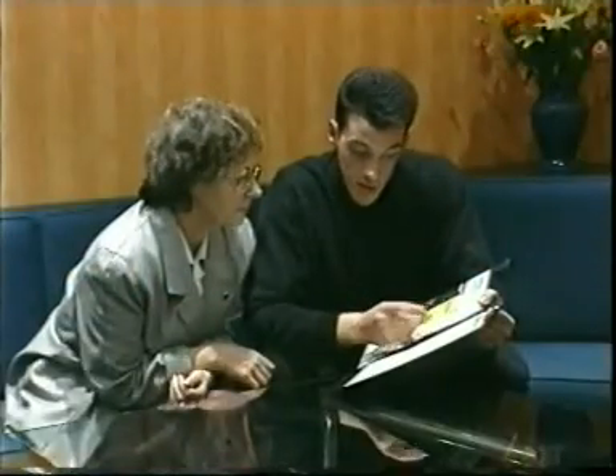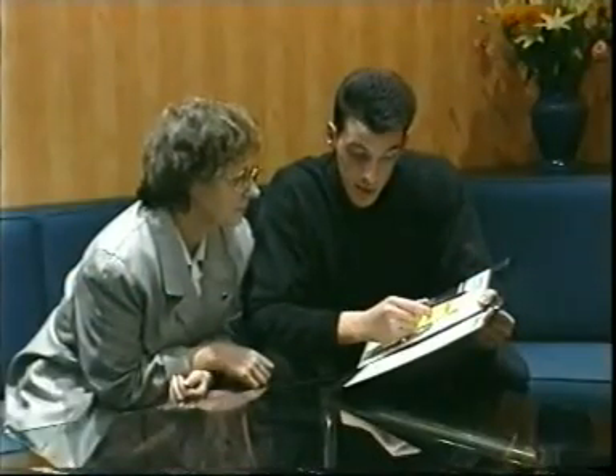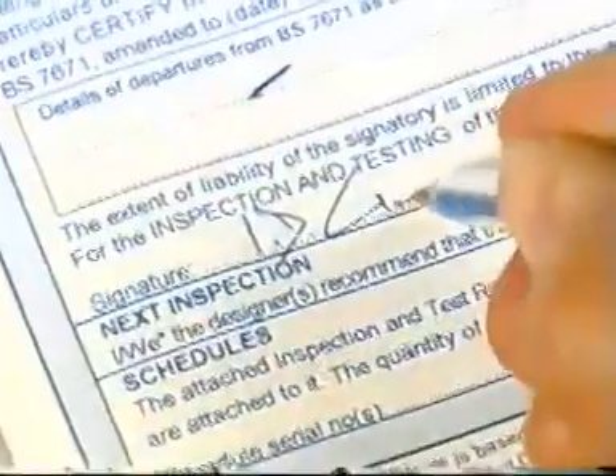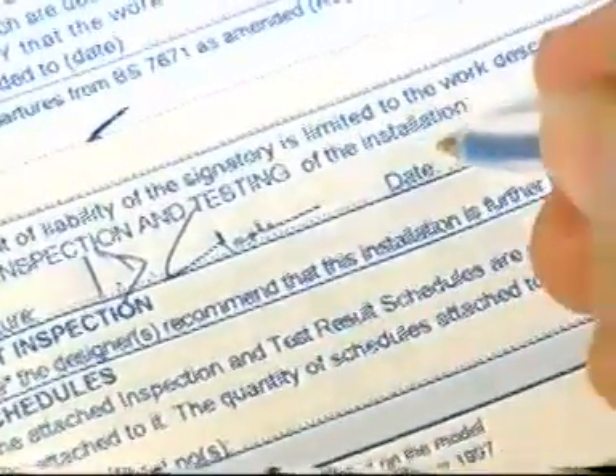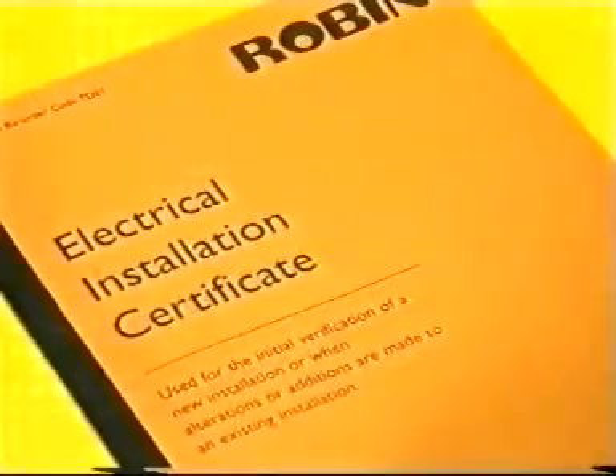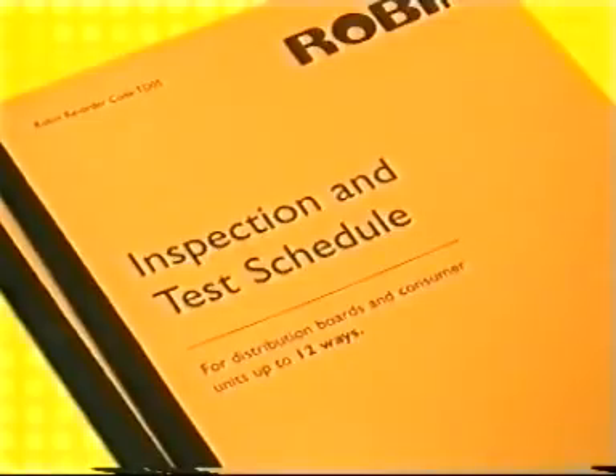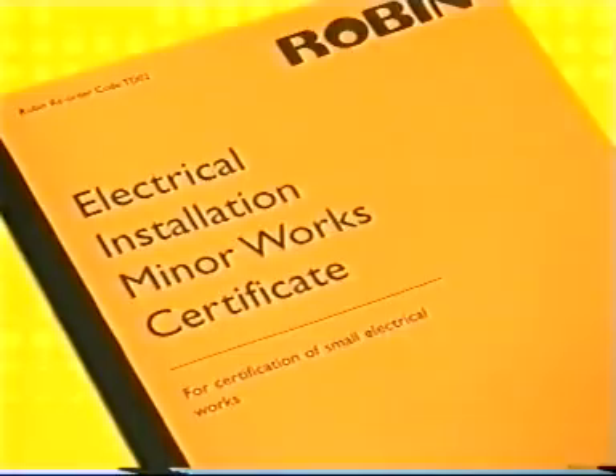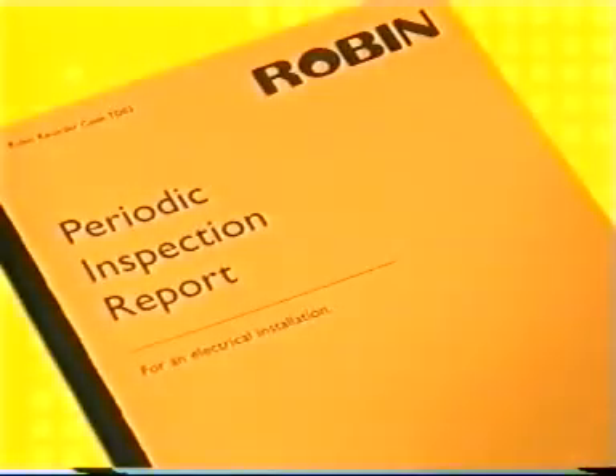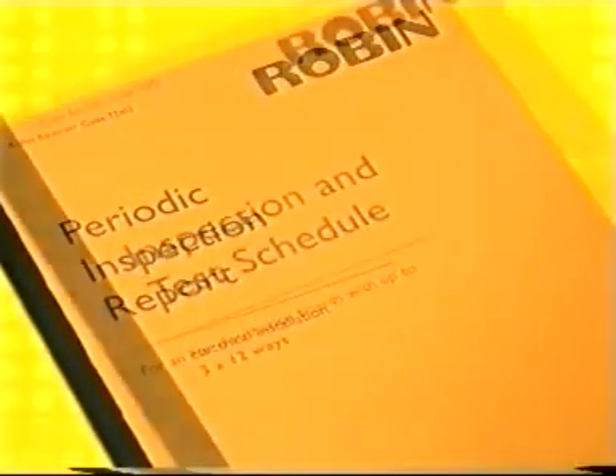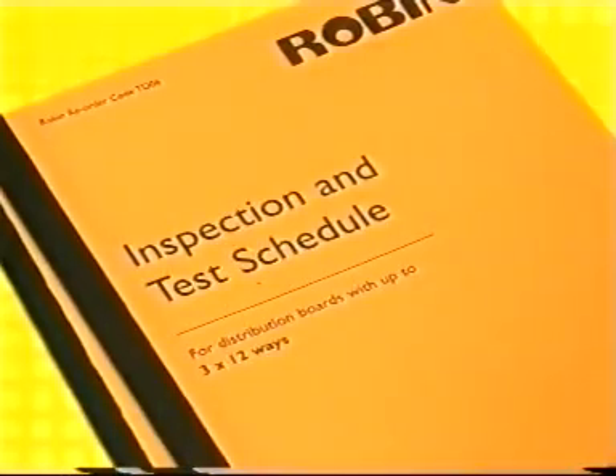During the construction of an installation and on completion of the inspection and testing activity, documentation must be provided to the person ordering the work. An electrical installation certificate and inspection and test result schedule must be provided for new installation work. An electrical minor work certificate is needed for minor alterations and additions which do not include the introduction of a new circuit. A periodic inspection report and inspection and test result schedule is required for verification of existing electrical installations.